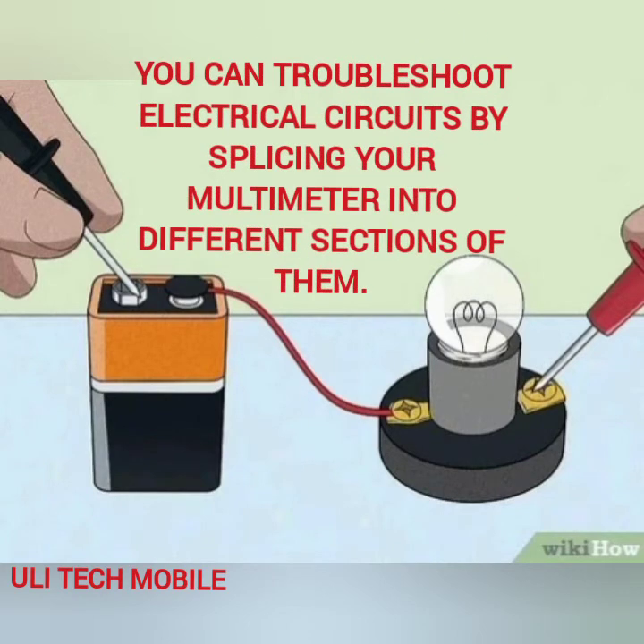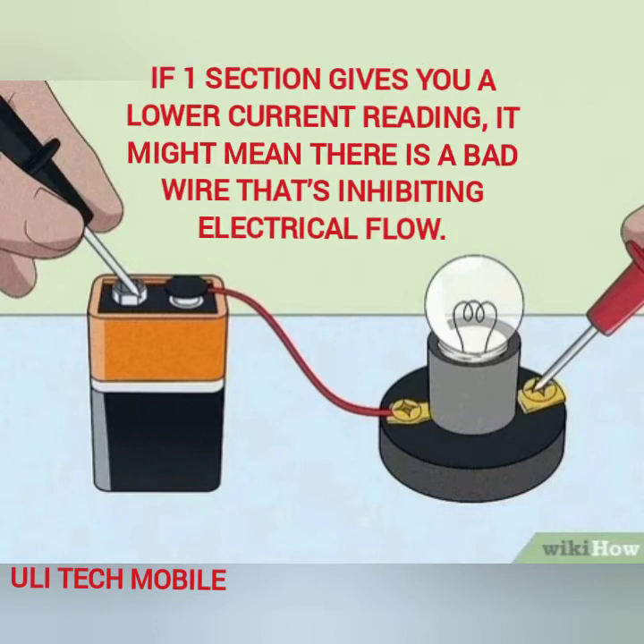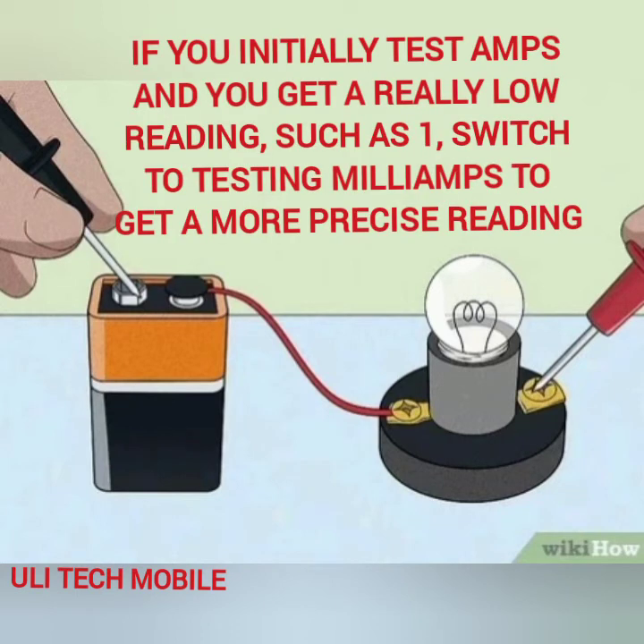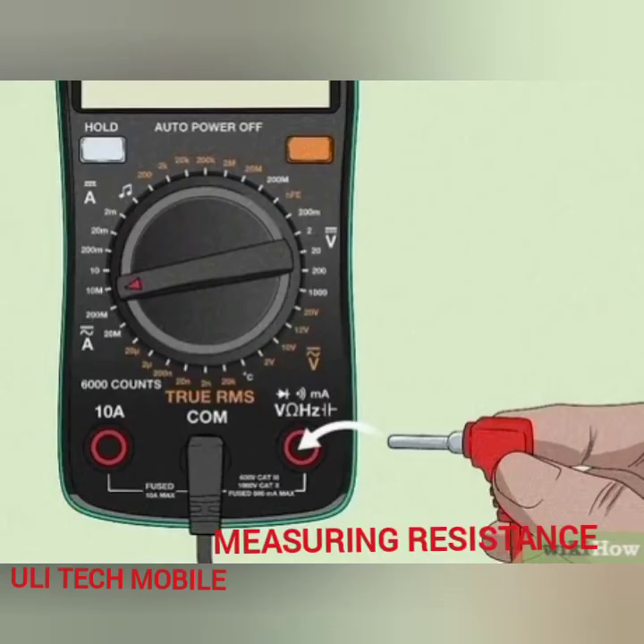You can troubleshoot electrical circuits by splicing your multimeter into different sections of them. If one section gives you a lower current reading, it might mean there is a bad wire that's inhibiting electrical flow. If you initially test amps and you get a really low reading, such as one, switch to testing milliamps to get a more precise reading.